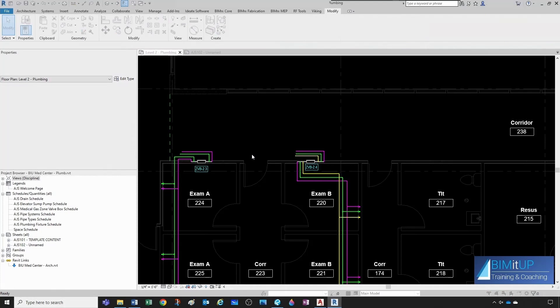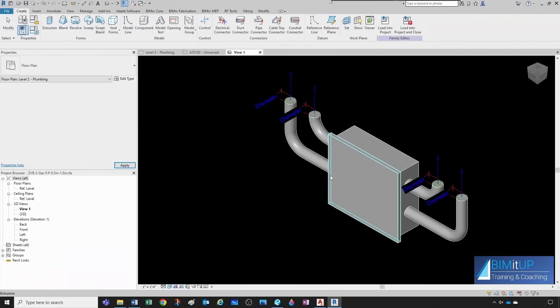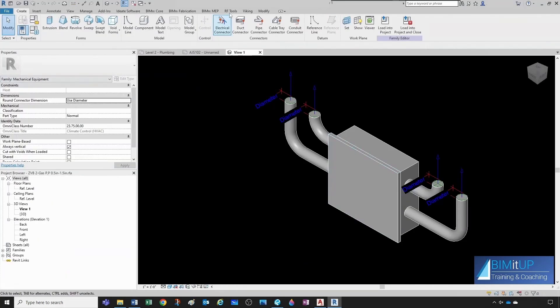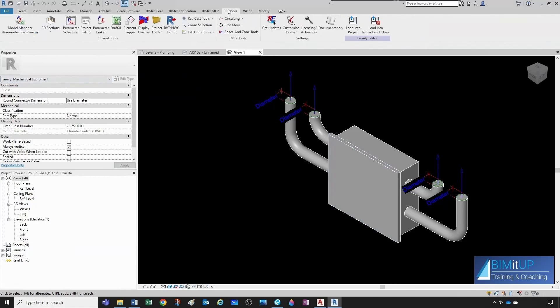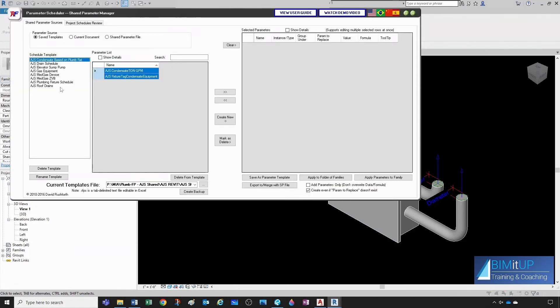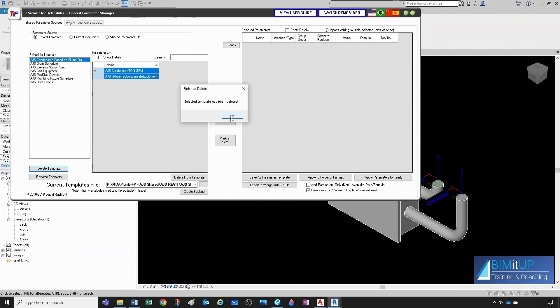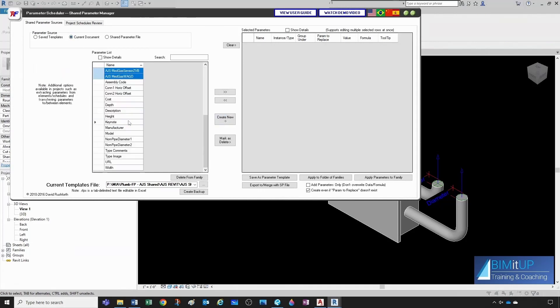Let's go to the other zone valve box so we can grab the parameters. And we come here to our tools, parameter scheduler. We get this medgas zone valve box. I'm going to delete this template because I'm going to create a new one based on the current document.